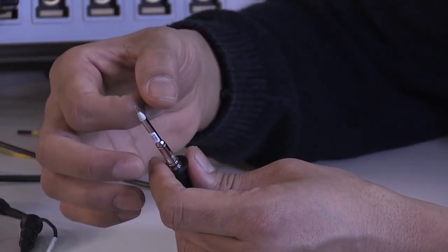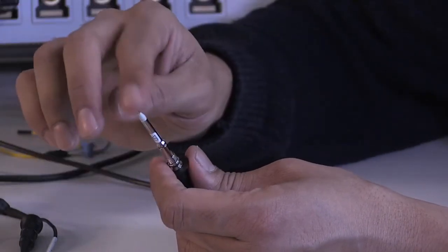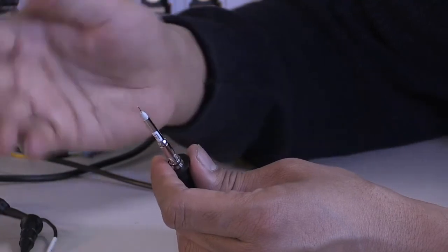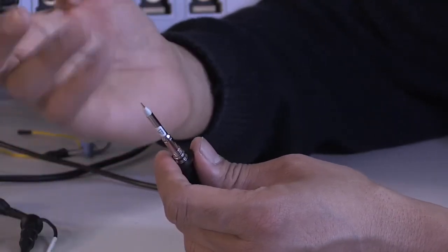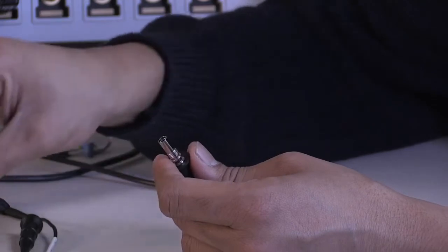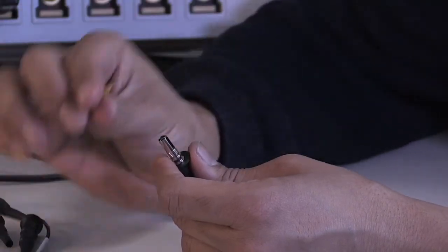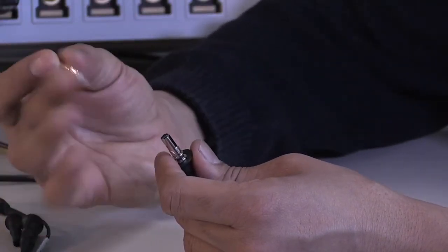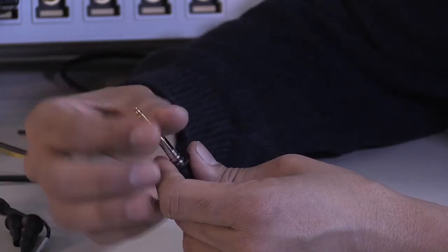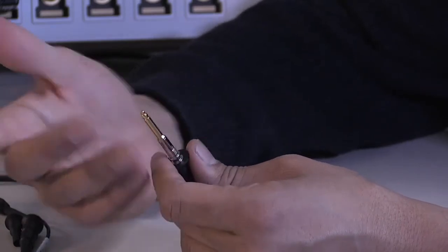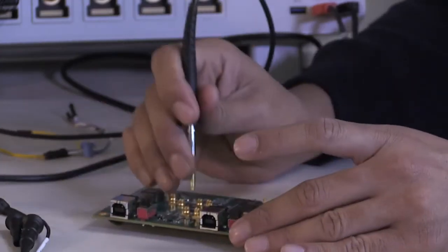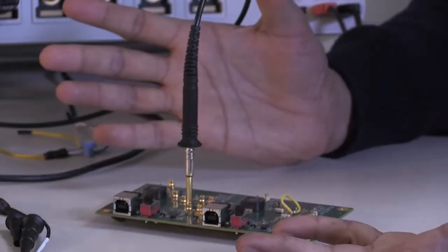And we are getting a lot of issues with this connector problem with this circuit, and that's why we came up with a solution for this, right? So this is pretty cool, right? What we did was we created an adapter. This is an MMCX adapter for the standard TPP1000 probes, and you essentially plug it in and you have this beautiful high frequency connector. So once you have these connectors, you can essentially just plug it in and there you have it.